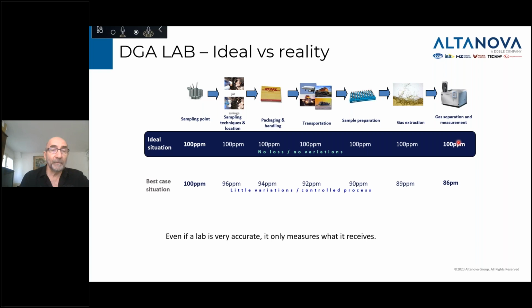So what is the reality? Well, in the best case situation, if everything is under control, you flush the drain valves before you take the sample, and you take a very high quality container, because there are containers and containers. Some of them look good, but they have absolutely no seal, especially for low molecular weight gases, so you lose them during transport.